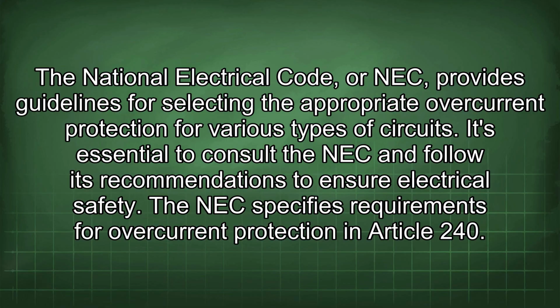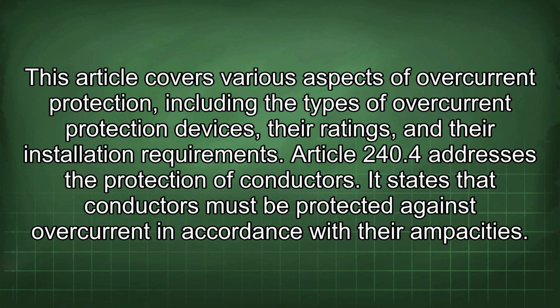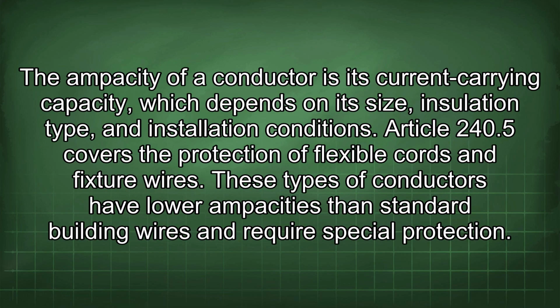The NEC specifies requirements for overcurrent protection in Article 240. This article covers various aspects of overcurrent protection, including the types of overcurrent protection devices, the ratings, and their installation requirements. Article 240.4 addresses the protection of conductors. It states that conductors must be protected against overcurrent in accordance with their ampacities. The ampacity of a conductor is its current carrying capacity, which depends on its size, insulation type, and installation conditions.